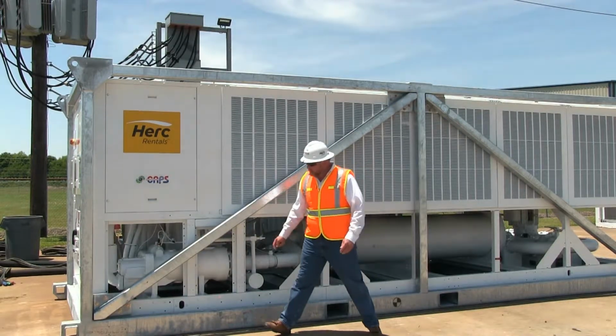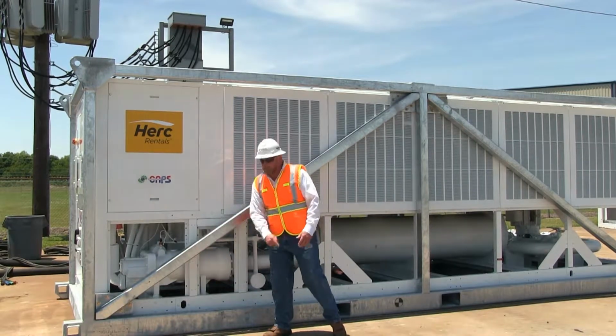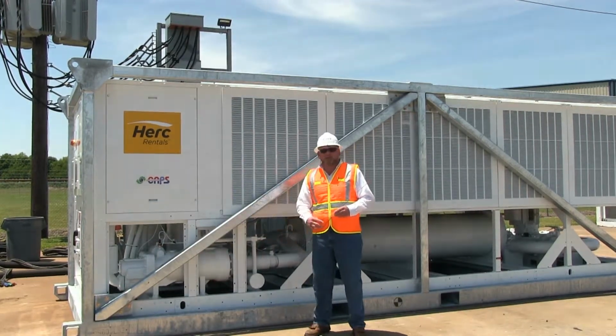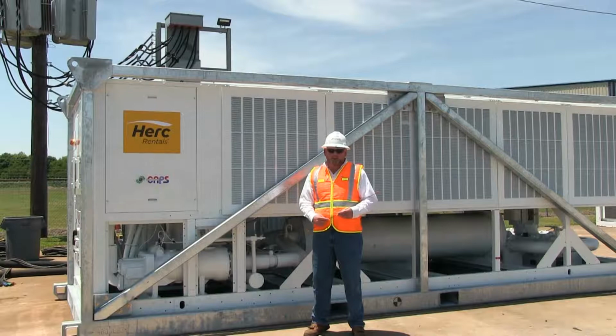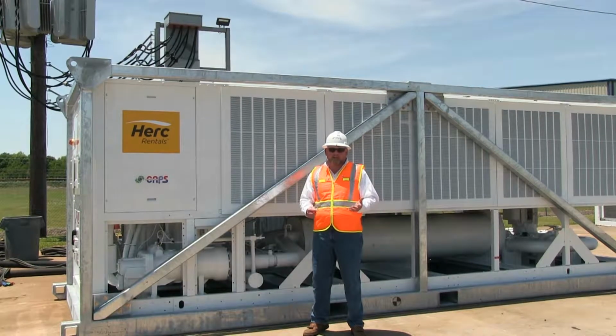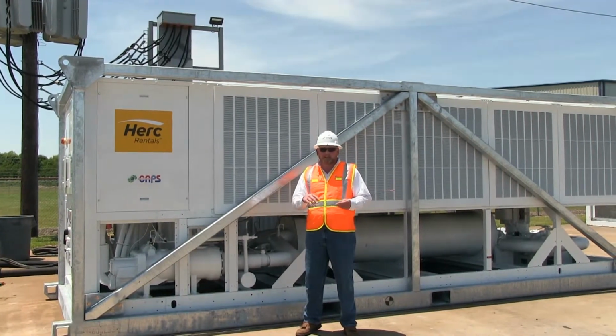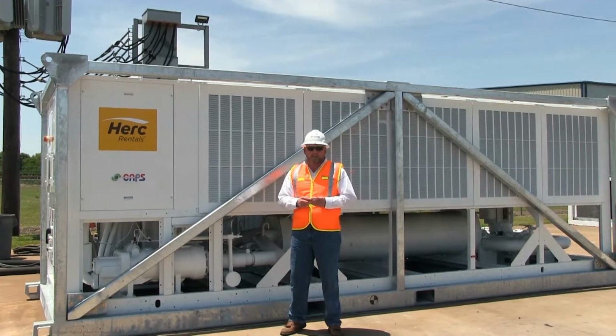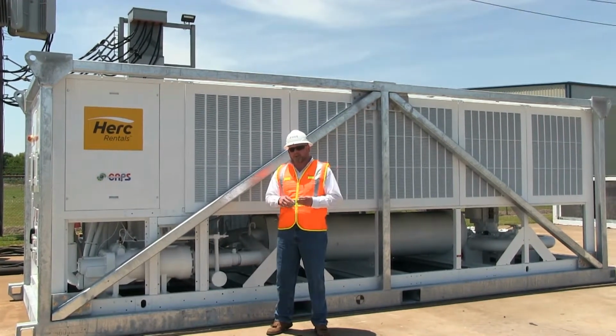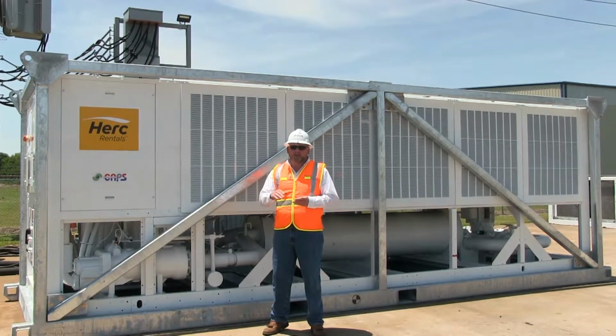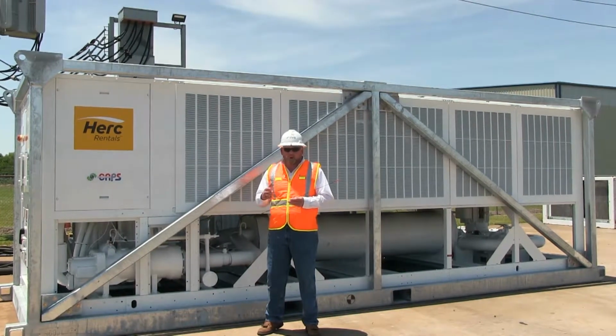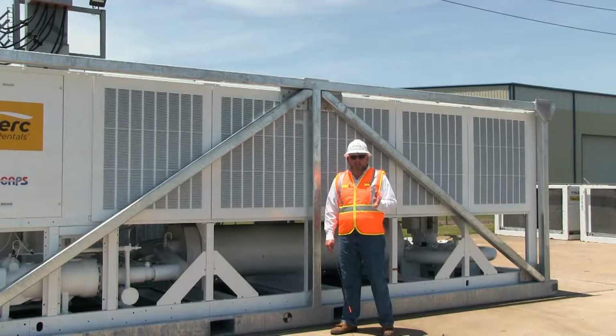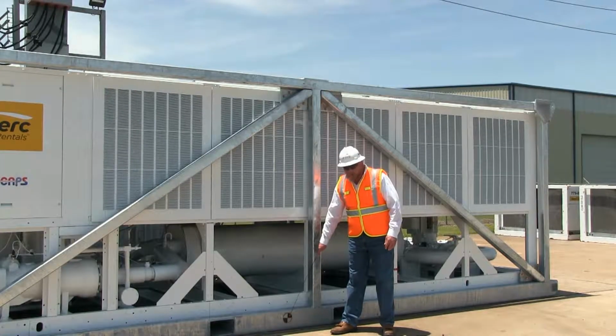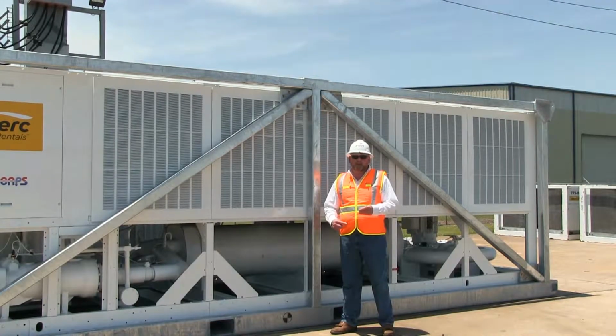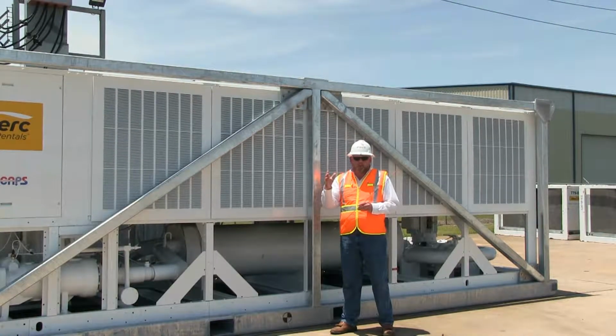Please note that the weight of the machines is always located on the stainless steel tag at the bottom corner. This particular machine weighs 20,000 pounds, so the proper crane or forklift will be necessary in mobilizing and setting the chiller on a particular job site. Please note that when you do set the machine on the job site, you need to make sure that it's on level, stable ground that can hold the 20,000 pounds of weight. For safety, the machine is marked clearly with the center of gravity on all four sides. That's going to be necessary for lifting it overhead with cranes or with a pick truck.